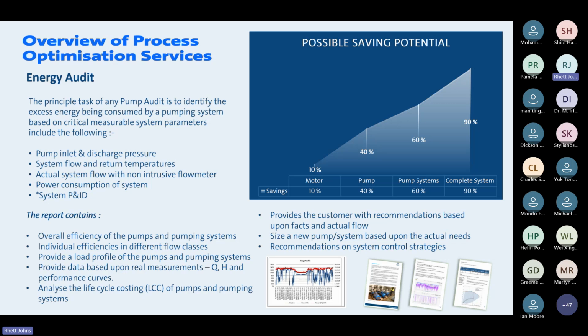So the system is resized. You might go with maybe a 3-pump system, and most of the time it runs with only 1 or 2 pumps. And then on the hottest day of the year, when you've got a cooling system and it's the middle of summer, we then bring on that 3rd pump, and that 3rd pump contributes to an extra flow. But we're not just running one massive pump all the way left of curve. So using this sort of method, and Grundfos does this as part of our team, we can then recommend a complete overhaul of the system, as well as add control strategies to ensure that we've got the system running at the best efficiency.